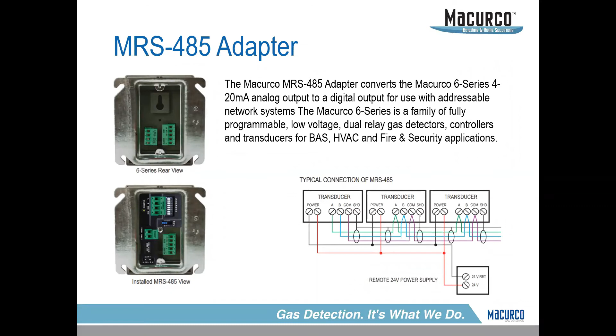The one thing that we stress, and the reason why we put this slide in here, is anytime you have an addressable system, which is going to be the bottom detector, what we do is we take our Modbus adapter, we plug it into the detector, and it takes an analog connection and makes it addressable. It still leaves you with those dry contacts. So for local notifications, so your local horn strobes, or maybe it's a local fan, or maybe a local switch, or whatever the type might be, that option is still available. So a lot of people have that question. It's pretty unique in how we did it and how we came across it, but it's still there. Again, this allows you for the addressable side on the bottom there, where you can daisy chain or connect them in series.